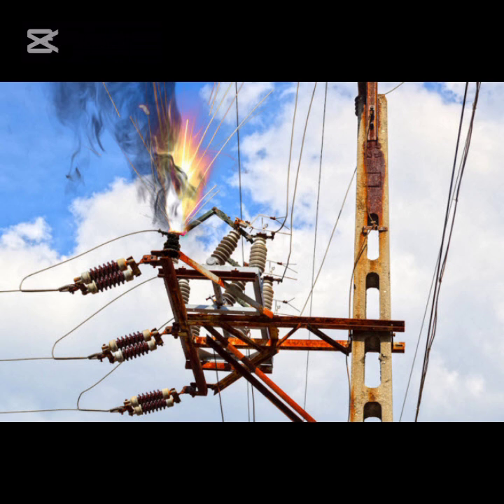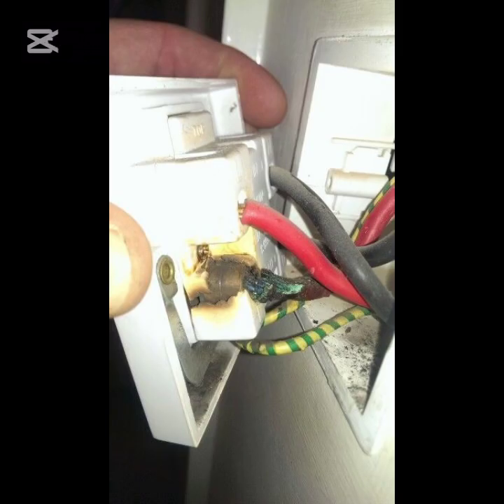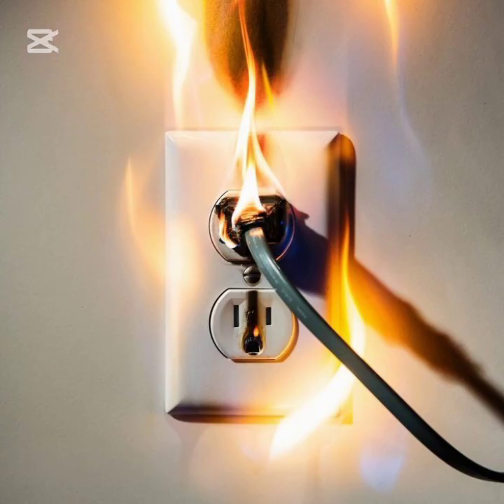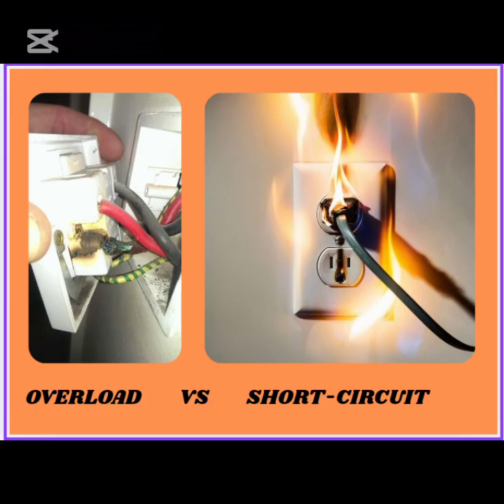Since we have understood what short circuit is, it's important to differentiate short circuit and overload conditions. An overload happens when the current exceeds the normal operating range but still follows the intended path. Whereas a short circuit diverts the current away from its intended path due to a fault, leading to much higher current flow, and posing a more immediate threat to system stability and safety. Although the current flowing through overloaded equipment is high, it still remains significantly lower than the current experienced during a short circuit.